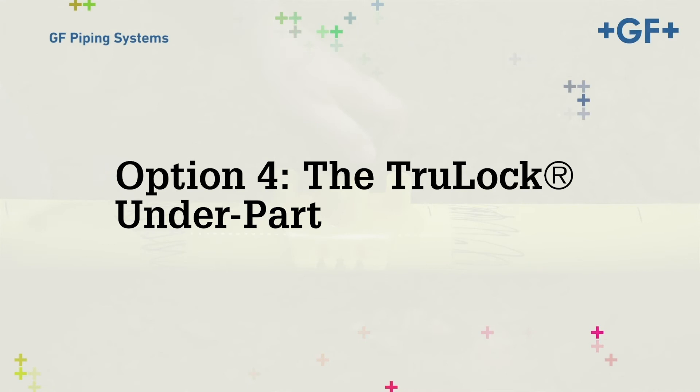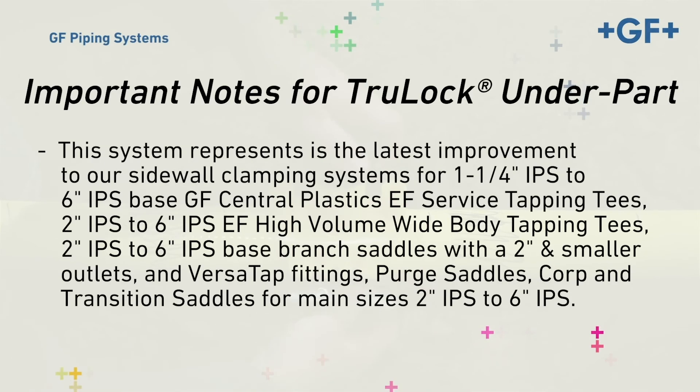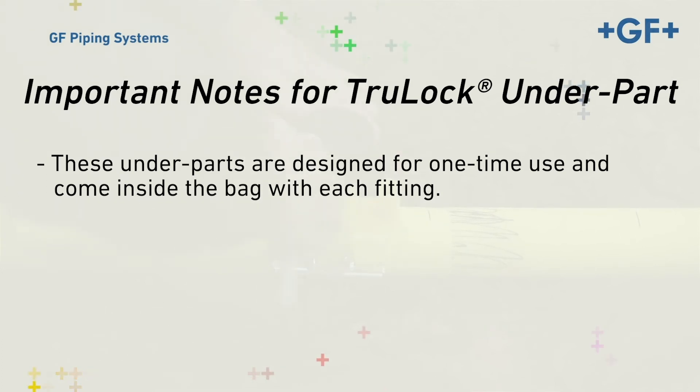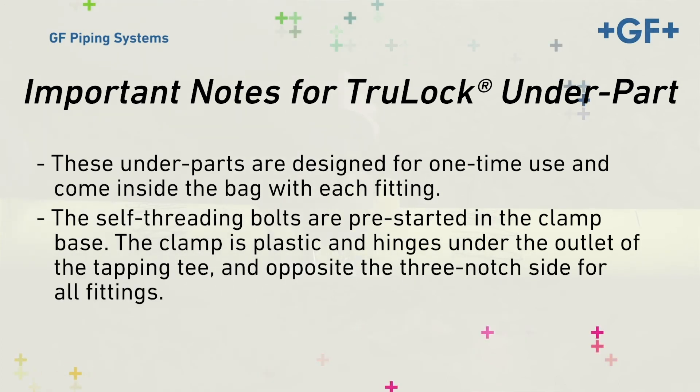Option 4: the TruLock under-part. This system represents the latest improvement to our sidewall clamping systems for 1.25-inch IPS to 6-inch IPS GF Central Plastics EF Service Tapping Tees, 2-inch IPS to 6-inch IPS EF High Volume Wide Body Tapping Tees, 2-inch IPS to 6-inch IPS Base Branch Saddles with a 2-inch and smaller outlet, and Versatap Fittings, Purge Saddles, Corp and Transition Saddles for main sizes 2-inch IPS to 6-inch IPS. These underparts are designed for one-time use and come inside the bag with each fitting. The self-threading bolts are pre-started in the clamp base. The clamp is plastic and hinges under the outlet of the tapping tee, opposite the three-notch side for all fittings.